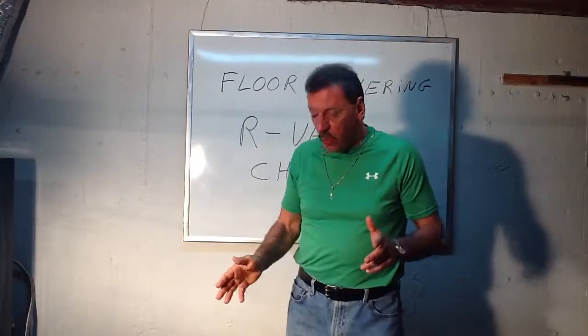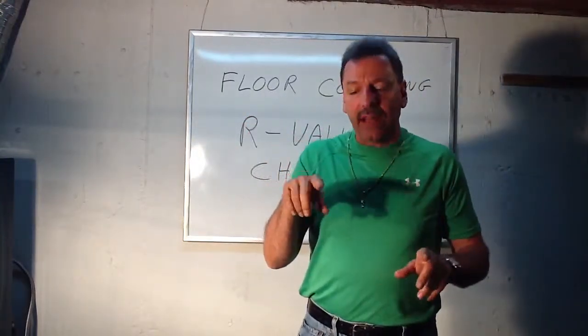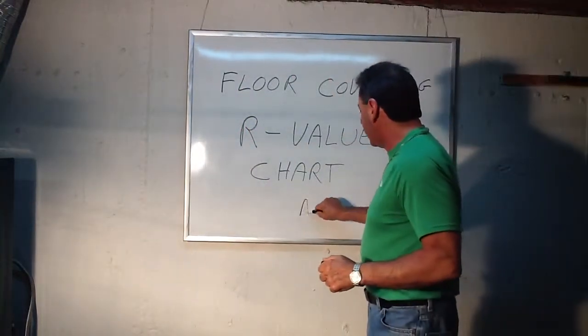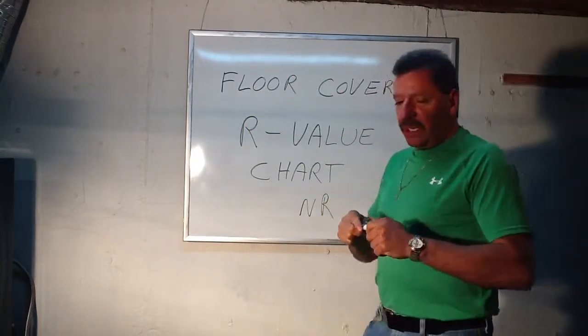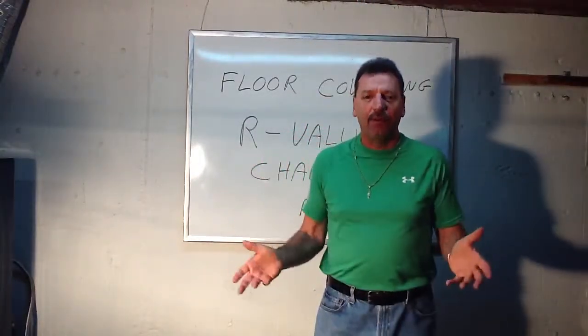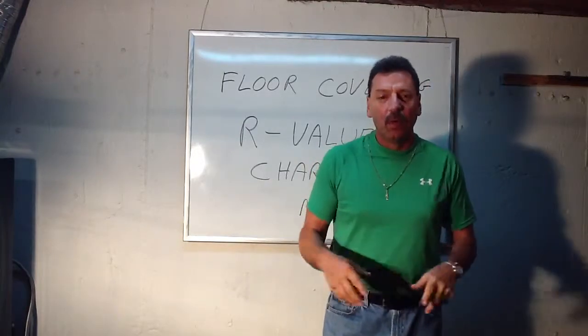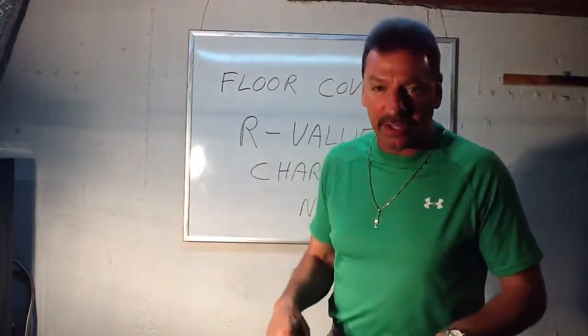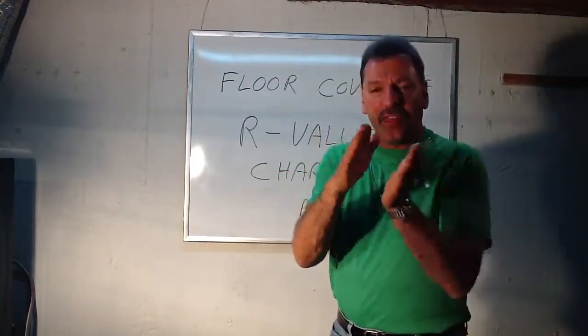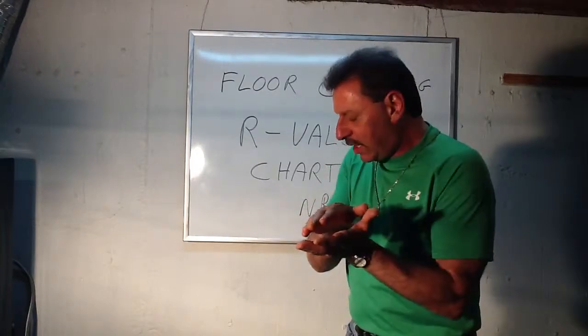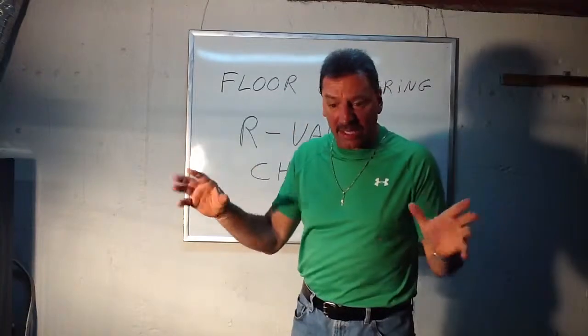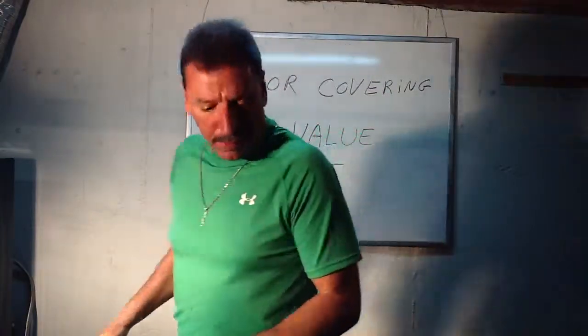It also goes up as far as one inch. You'll see a lot of NRs — NR meaning not recommended — because one inch thick carpet is almost impossible to get radiant heat through well enough to heat a room. One inch thick anything other than mud floor and tiles is kind of hard to get radiant through. I just want to show you how the thinness versus thickness on the chart affects R-value numbers drastically. So I'm going to bring you over to the chart.